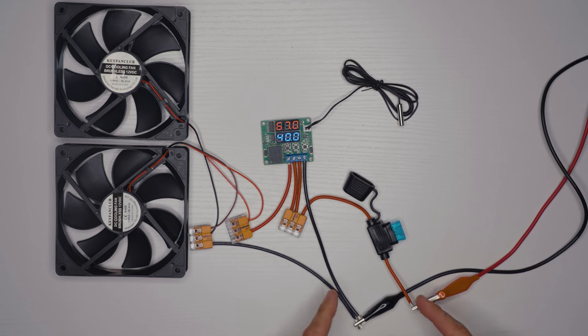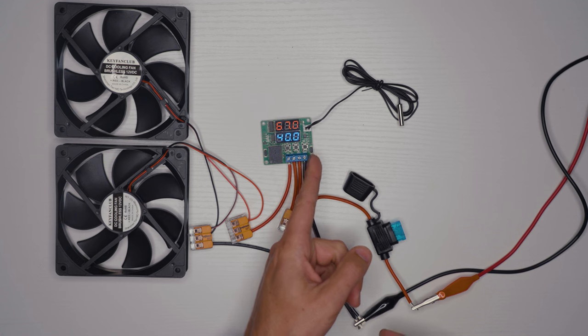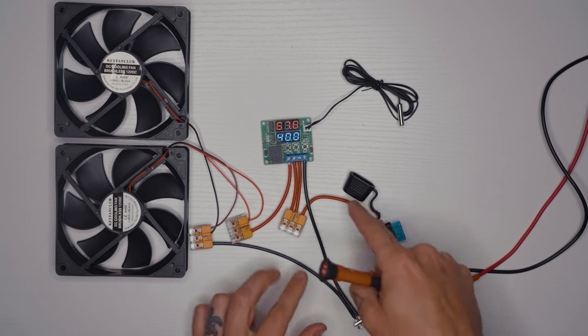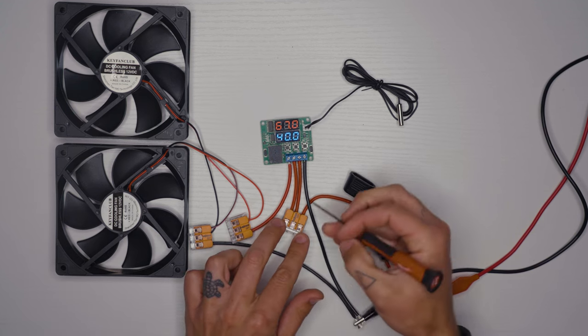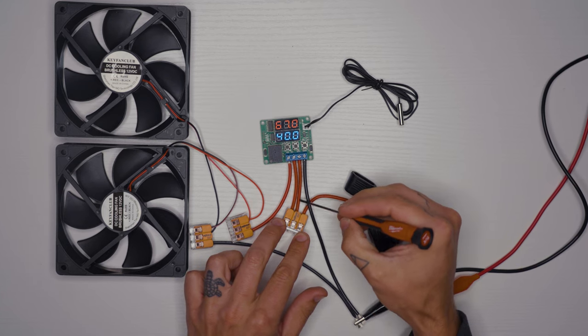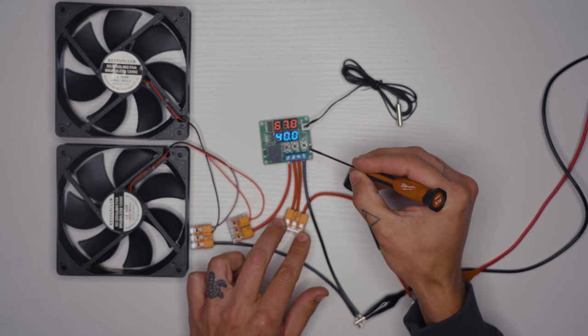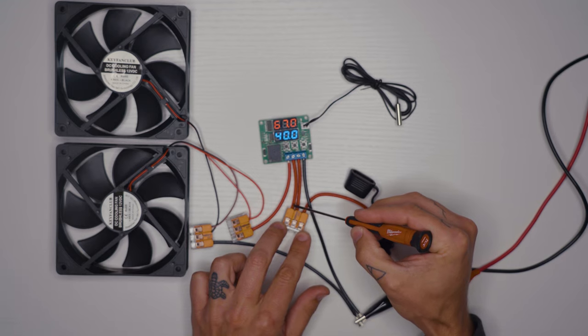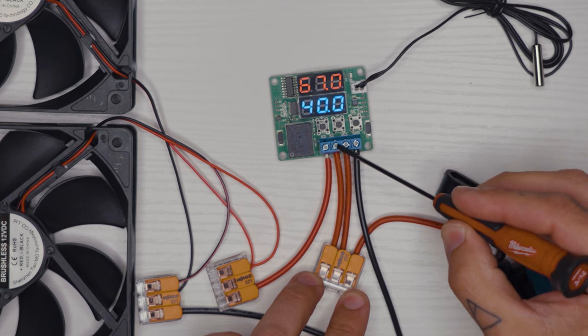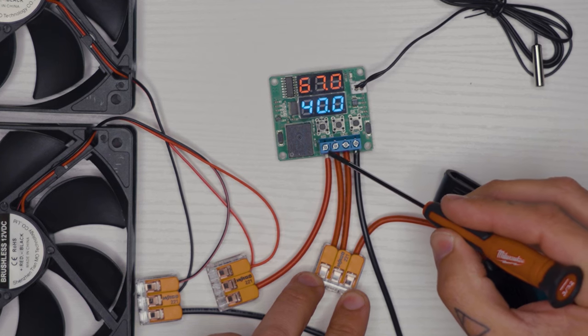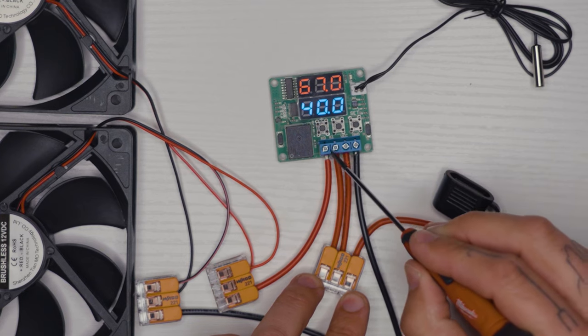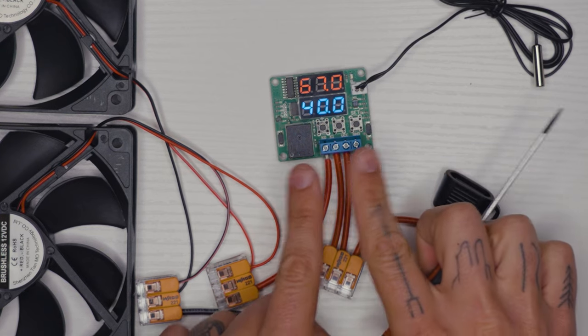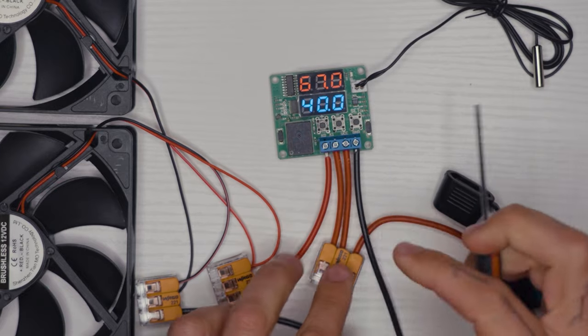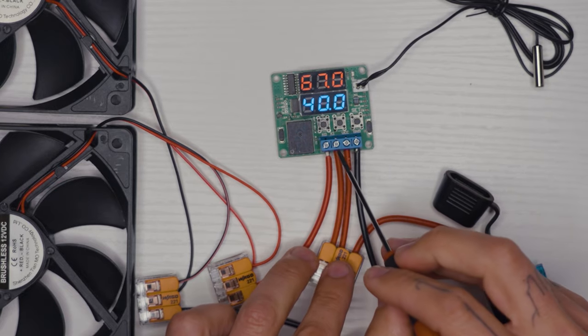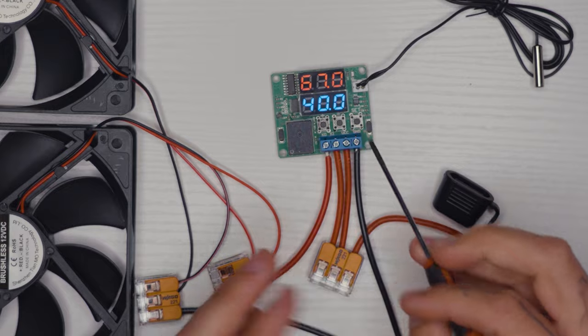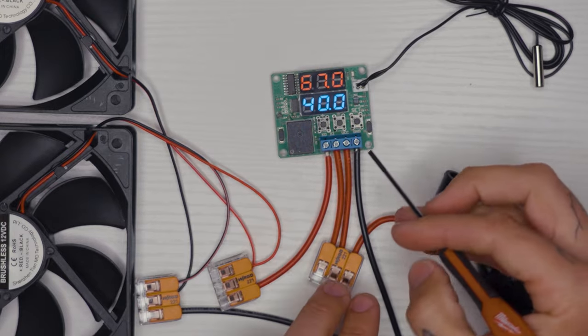So we've got negative coming to the terminal, and then we've got positive coming into this lever nut, and one of them is powering the thermostat itself, and the other is coming out and through the switch part of the relay. These two terminals are simply connecting or disconnecting these two wires whenever the temperature gets to the temperature that we're going to set here in a minute.